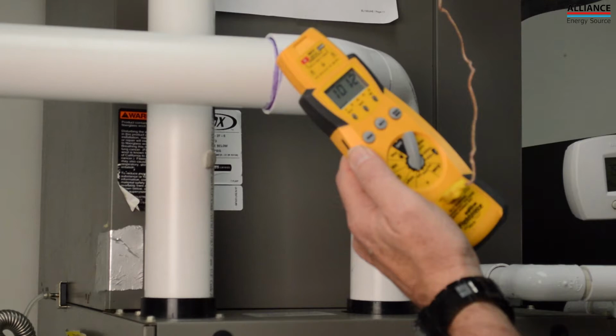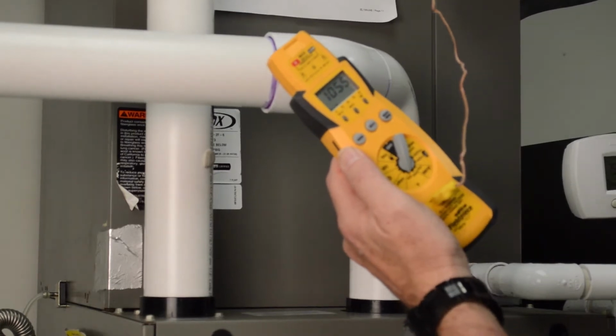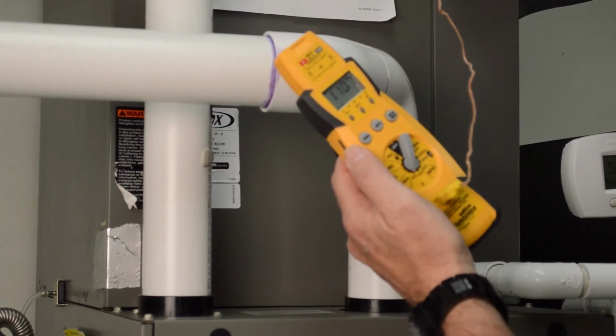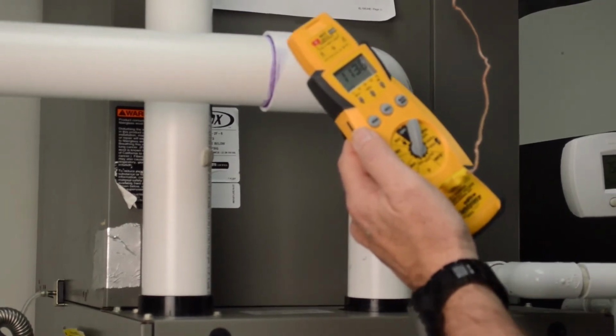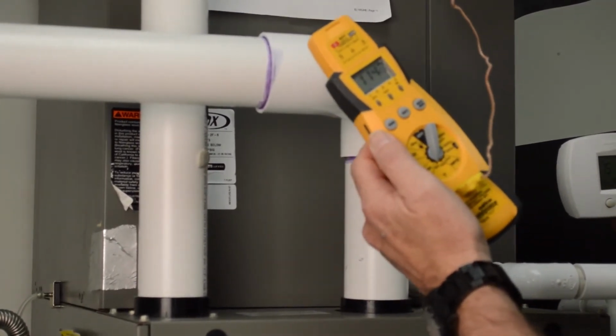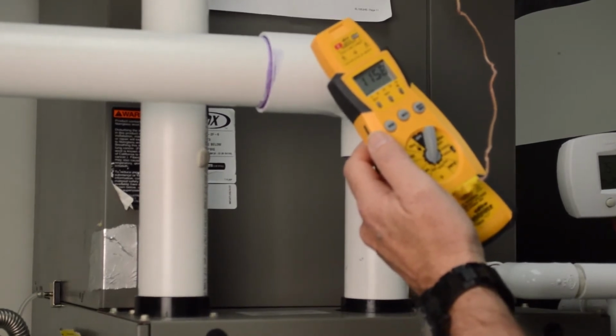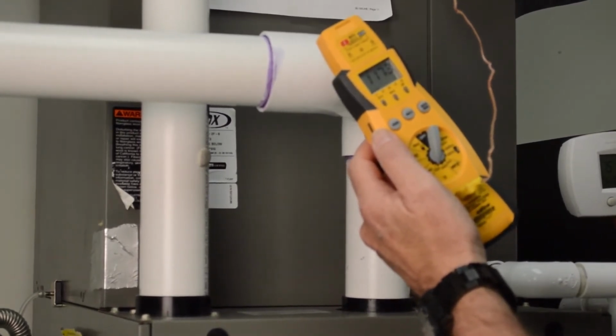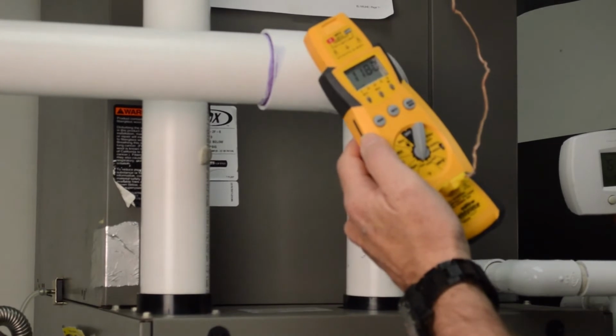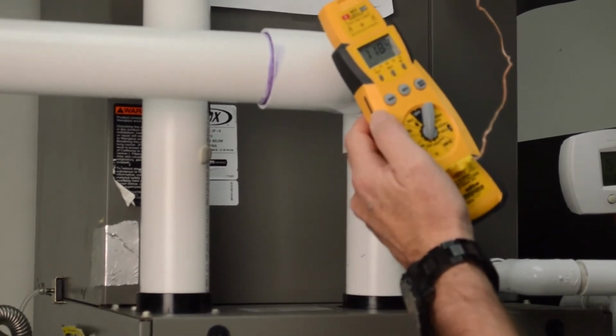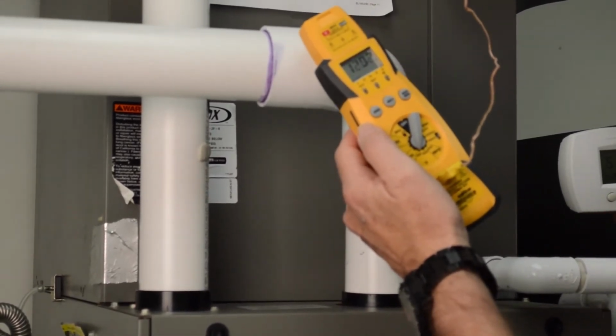We're going to do this again, out of line of sight on the supply side. On the other side of the coil is acceptable, but not in direct line of sight of the heat exchanger. The coil is going to absorb the extra heat picked up. The evaporator coil is going to pick up any radiant heat coming off the heat exchanger.